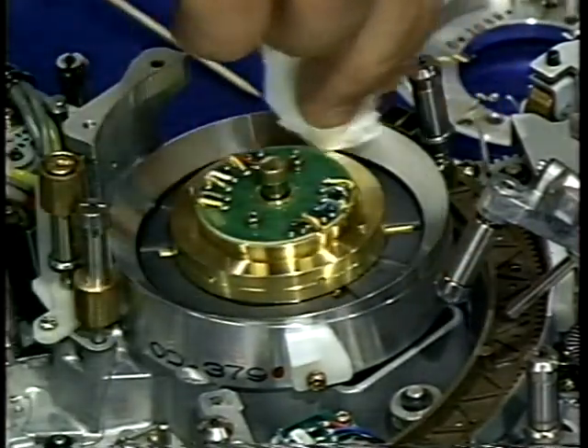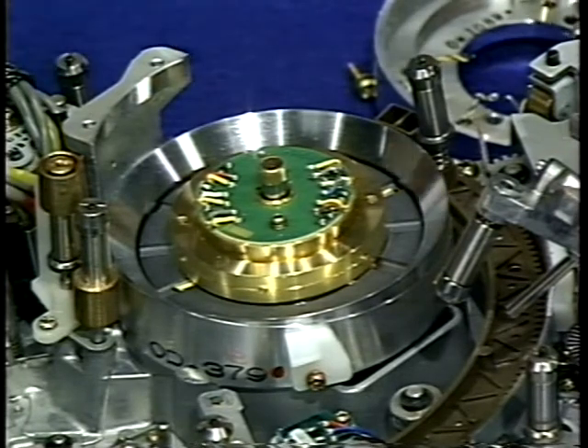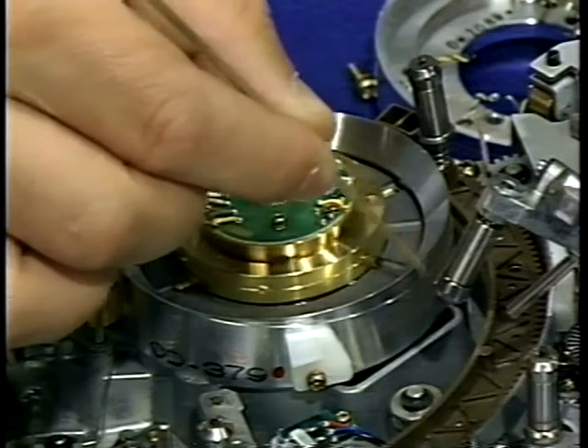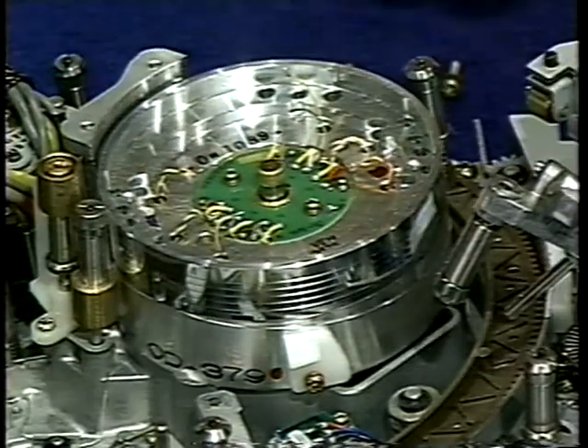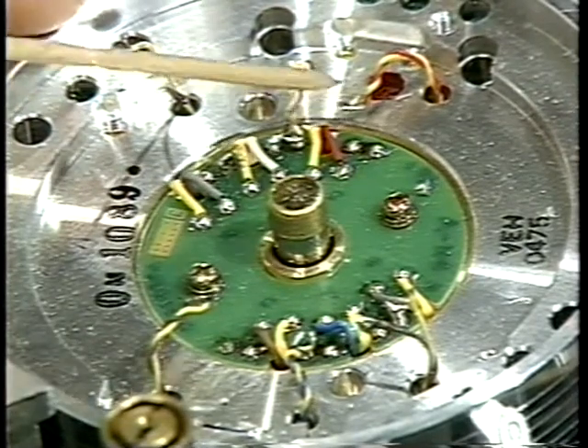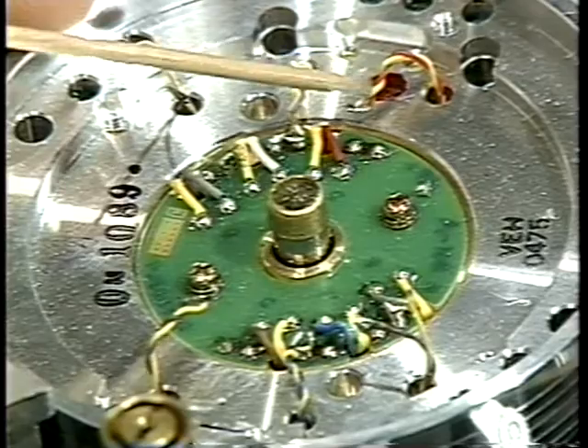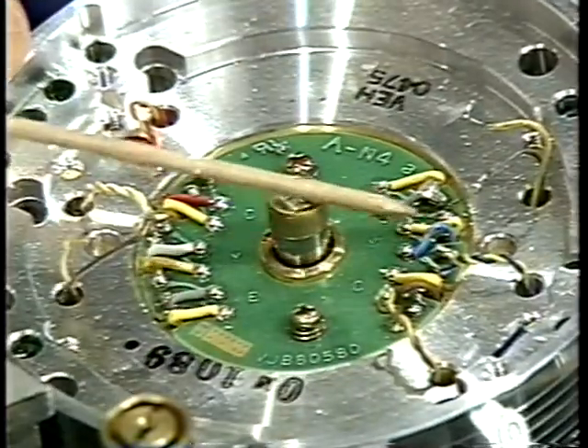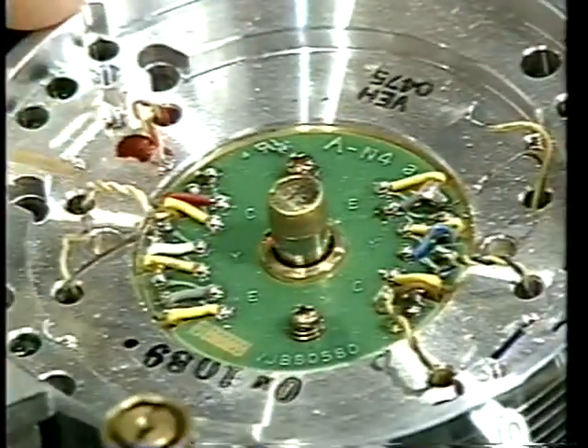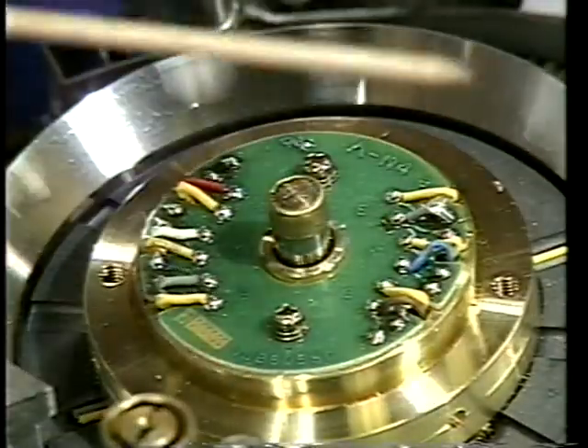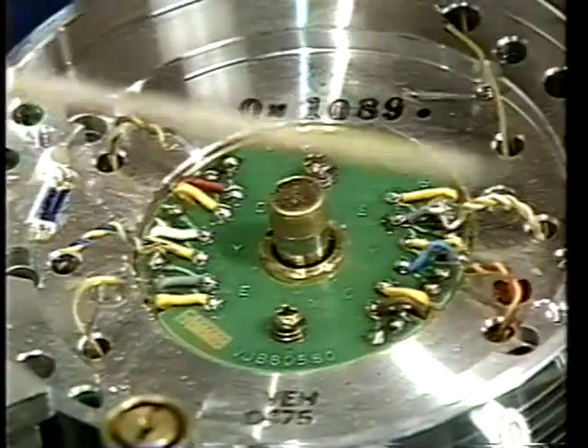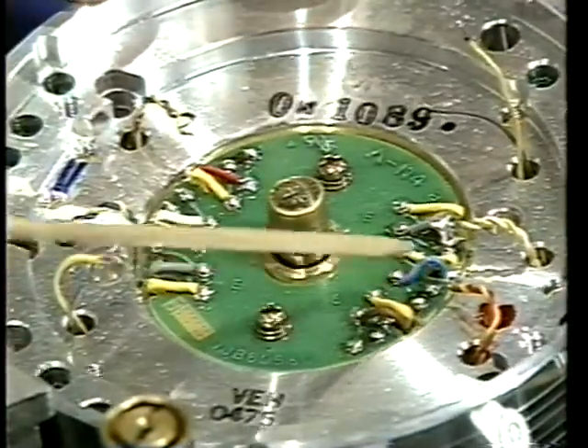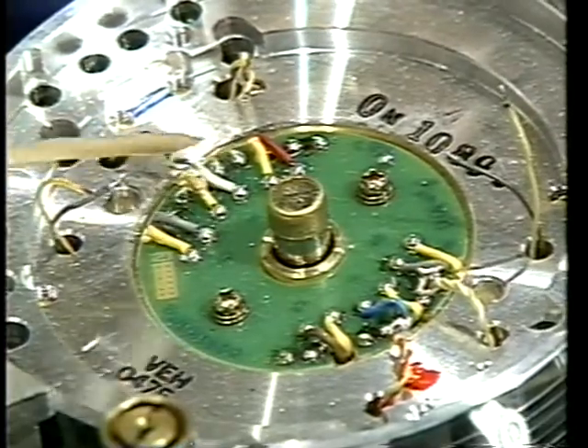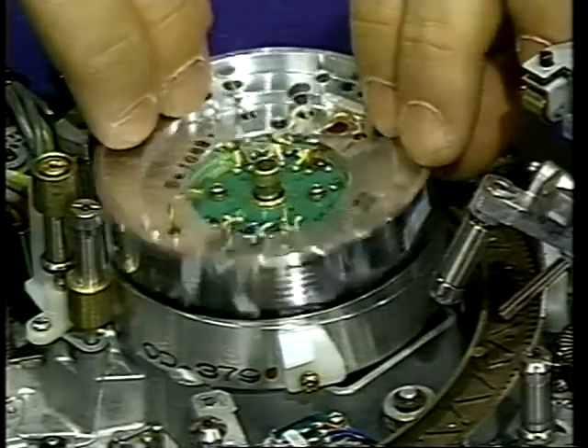Upper drum reassembly. Before reassembling the upper drum, clean the lower drum. Check for any scoring or other physical damage on the lower drum. Now replace with a new upper drum assembly. Note that it is important to match the color-coded wires, red and yellow, shown here, and blue and yellow, shown here. If the wires aren't matched, the fields will be reversed, causing problems. We can see that in this case the colors are not matched. So we need to rotate the drum 180 degrees so that the colors match.